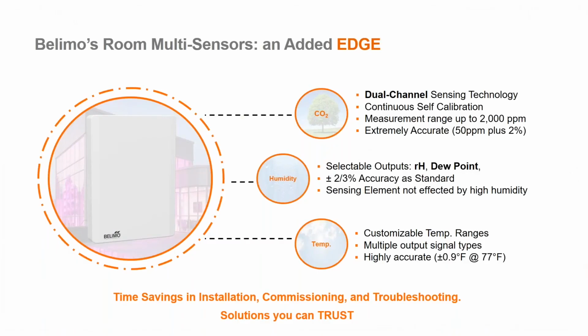One quick slide here to sum everything up. With our multi-sensors, you get an added edge with Belimo's products. The multi-sensor has CO2, humidity, and temperature measurement capability. On the CO2 side, the sensor itself is a dual channel sensor, which means that typically in the field, CO2 sensors drift over time. With our dual channel technology, the sensor is continuously self-calibrating. This eliminates the need to bring in any outside or third-party people to calibrate. Your sensors are always running, always operating, and always calibrating themselves throughout their lifespan.